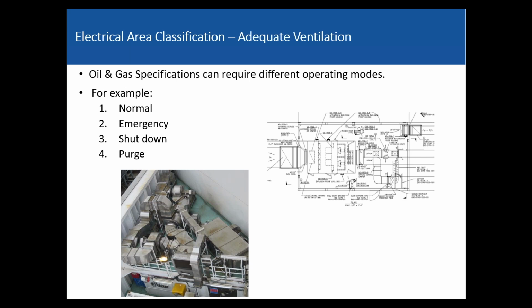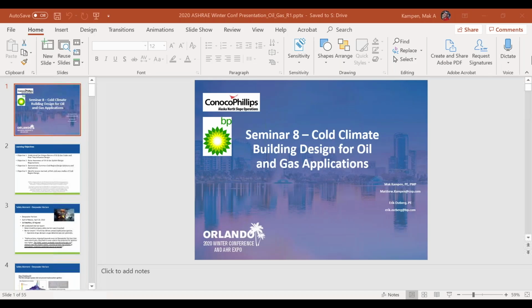Okay, operating mode. So we do design, and one of the differing things is different modes. You've got a normal mode, where we operate normally. You've got an emergency mode, where a plant upset, something happened. Shutdown mode: okay, we're planning to shut down, but we've got to shut down nicely, or else bad things can happen. A purge mode, where for either a gas event or smoke from a fire, we're going to purge the space. You've got these different modes, very common in our industry. We think about the different modes of operation, but you'll be shocked at how many people do not. They just think, oh, what's the flow rate? What's the static condition?